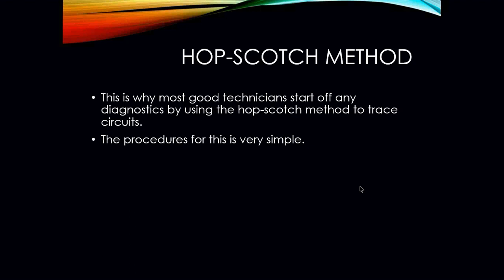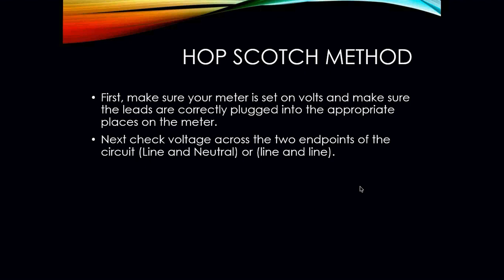Now, with the Hopscotch method, it is really important to understand that this method only works on 120 volts and below. Okay, so in HVAC, a lot of residential pieces of equipment will work off of 120 volts with 24-volt control circuits. So the Hopscotch method is a reliable way of troubleshooting. If you have a 208, 230, 480 system, the Hopscotch method really does not work so well. You do have to troubleshoot it slightly differently.